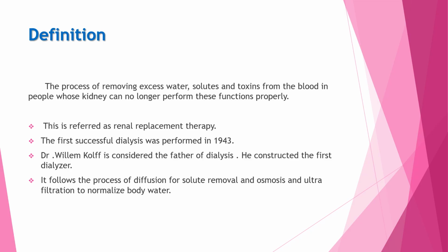The first successful dialysis was performed in 1943. Dr. William Kolff is considered the father of dialysis. He constructed the first dialyzer. It follows the process of diffusion for solute removal, and osmosis and ultrafiltration to normalize body water.